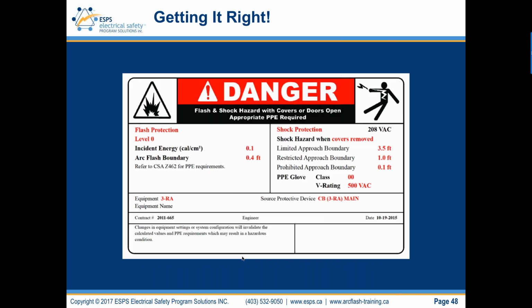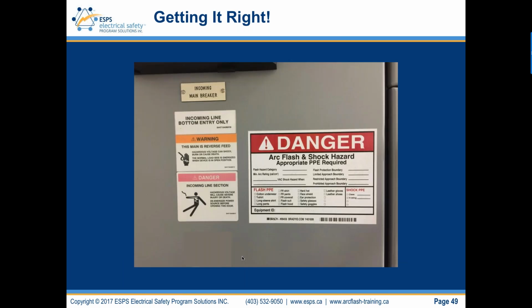This label is unbelievable. It's crazy. The language on here doesn't even match Z462. Now, again, the language has changed in Z462 and 70E, so you will find some labels that use old language, flash protection or arc flash protection boundary, right? But nonetheless, it says level zero. What's that? This label is not a good label. Here's a label that had something written on it, but the writing's faded. So you've got basically a blank label.